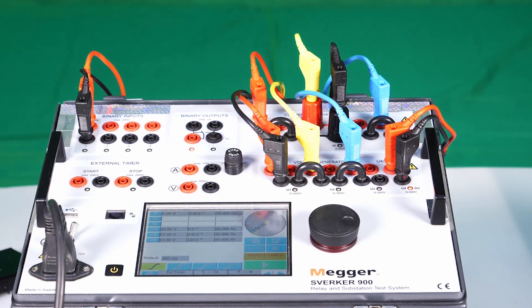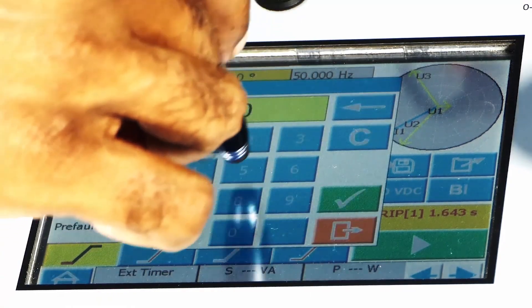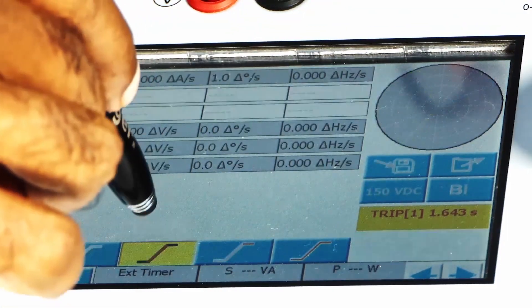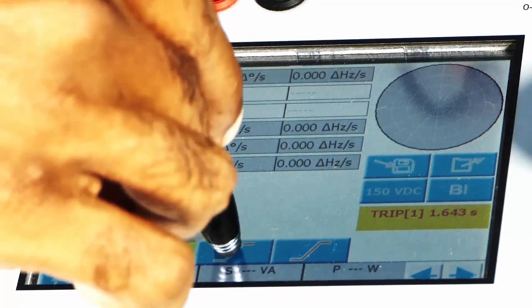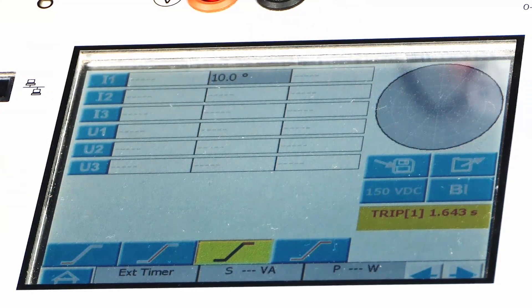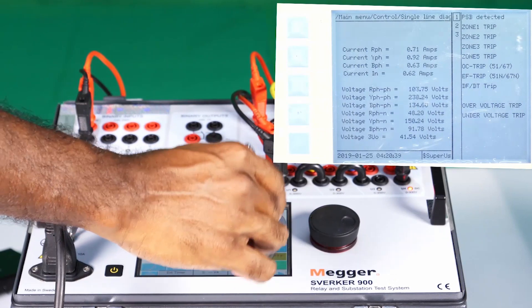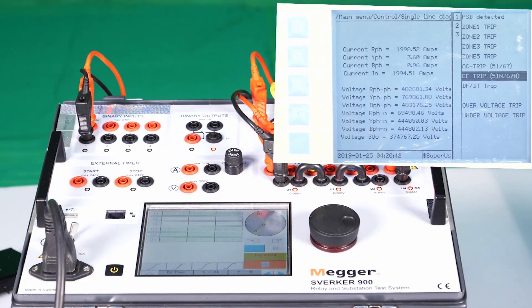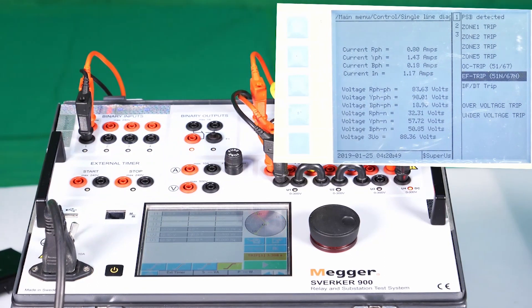The phase angle is ramped from 33 degrees down to 10 degrees, decrementing in steps of minus 1 degree. Now let's run this and verify the operation of the relay. It's expected to operate around 30 degrees. The actual operation is observed at around 29.7 degrees.